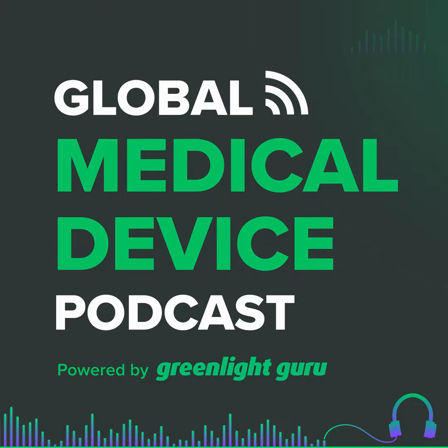I appreciate it. I'm glad, as always, to have this opportunity to share this information with you and your audience. Regrettably, I see so many companies, in some cases the largest medical device companies on earth that have hundreds and hundreds of regulatory folks on their team, and they make some of the most basic, elementary school level mistakes. So I'm happy to share the information. And rather than reiterating everything that we just talked about, I think the couple most important messages that people should come away with is, number one, if you're going to need clinical data for your medical device, and remember, not all devices do. Most 510K devices, in fact, do not need clinical data.